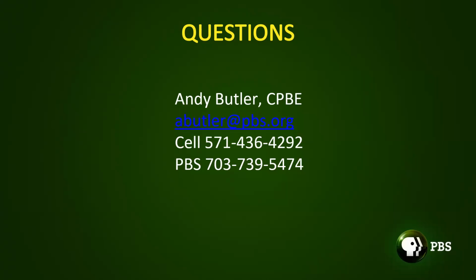Another question I had was about checking phase jitter. I know we ran into this once at a station in Macon, Georgia, where they had harmonics going on in the building causing havoc with the remote control system and automation systems. It turned out to be phase jitter between the phases. So how do you actually check that?